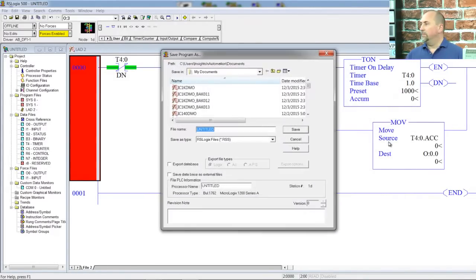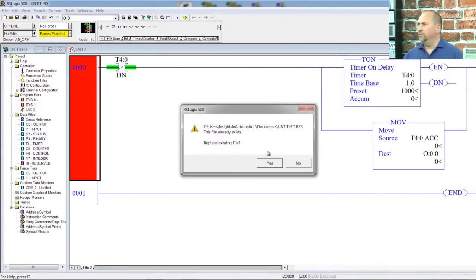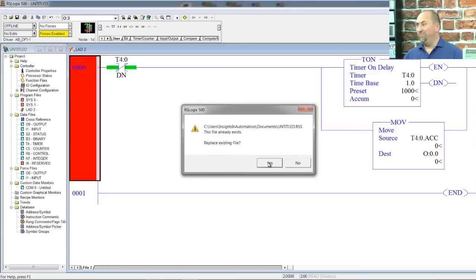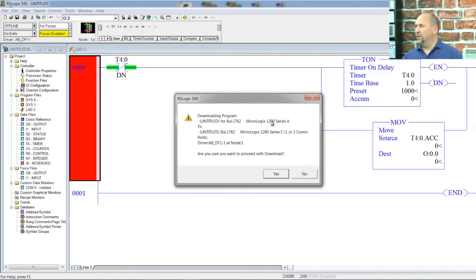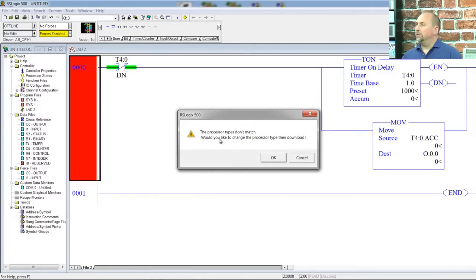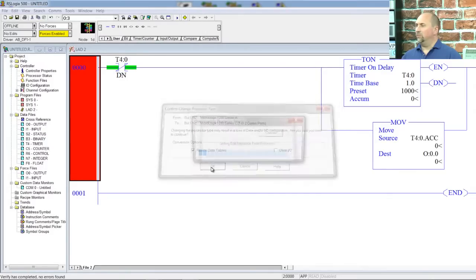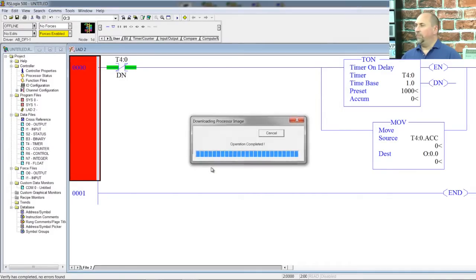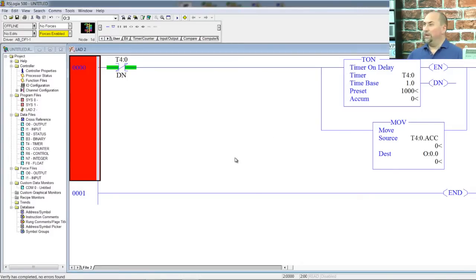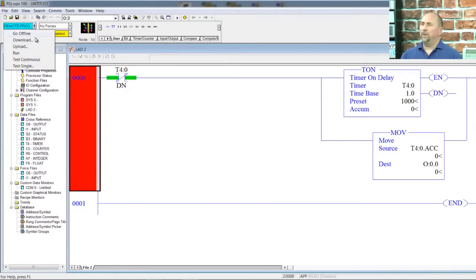Then we can click on Download. The software asks if I want to save it first — yes. Replace the existing file with the same name — yes. Now it's saying I chose the MicroLogix 1200 Series A, but what I actually have in the field is a Series C with a program already in it. Do I want to overwrite and still download? Yes. The processor doesn't match — would I like to change my program to match what is in the controller? Yes. It's going to make the change and now it's downloading my program. And now it's asking if I want to go online — sure, why not. Boom, we're online.